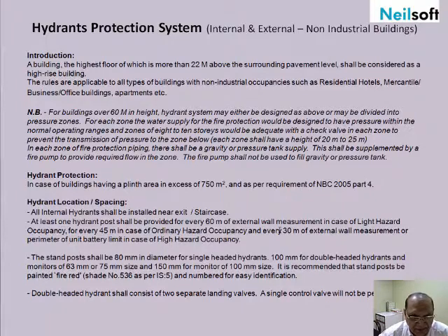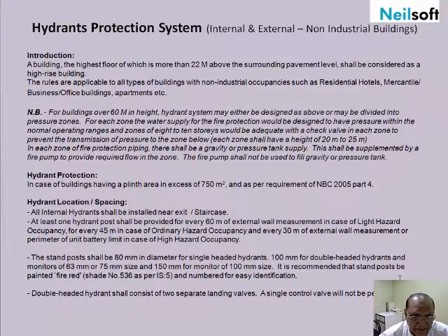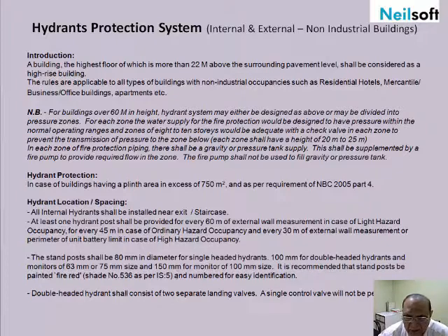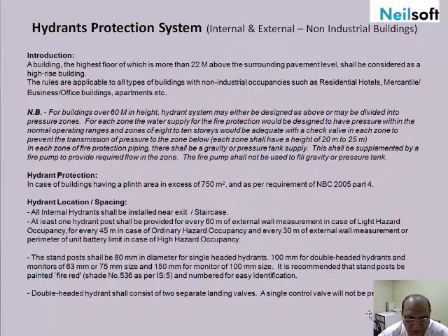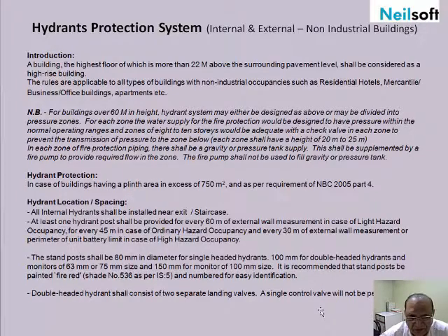Regarding the standpipe: external hydrants must be mounted on a pipe with a minimum diameter of 80 millimeters for single-headed hydrants, and 100 millimeters for double-headed hydrants. For monitors of 63mm or 75mm, it should be 75 millimeters diameter. Double hydrants shall consist of two separate landing valves — a single control valve will not be permitted. This means each hydrant should be separated by a separate valve for the purpose of maintenance and use.